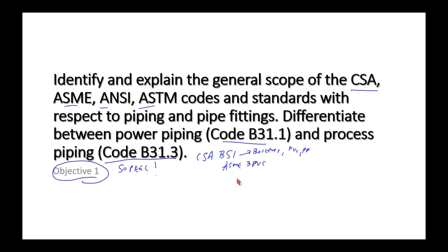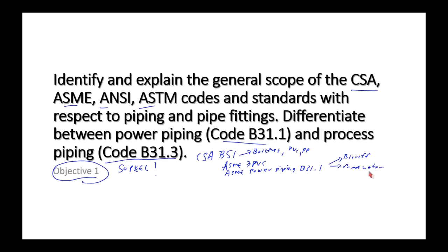There's something specific to boilers that we don't find in the Boiler Pressure Vessel Code — that would be the ASME Power Piping Code, B31.1. That's where we find information about blow-off piping, feed water piping, and instrumentation piping. The most important ones are boiler blow-off and feed water. It specifies what kind of valve, what kind of piping, and what design considerations apply.